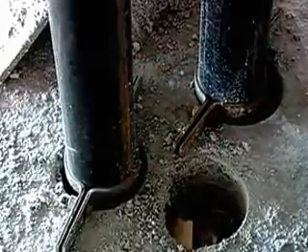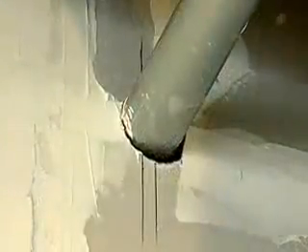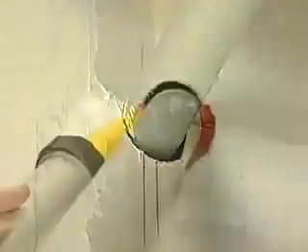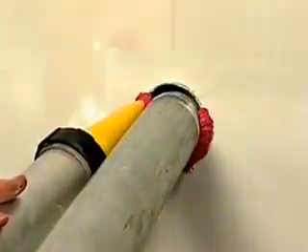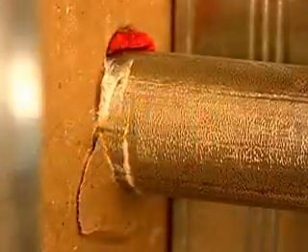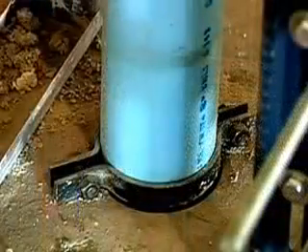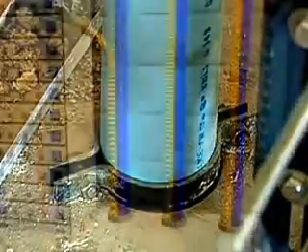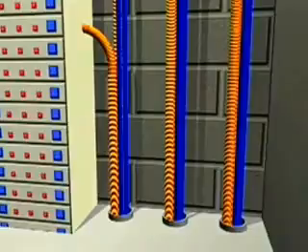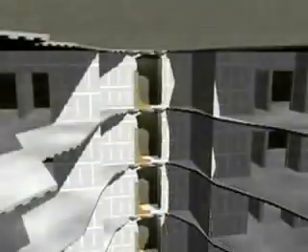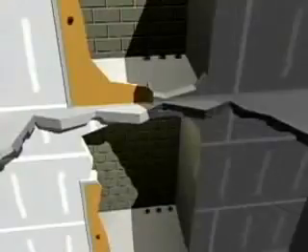Non-combustible penetrations like steel pipe and conduit are difficult enough themselves to deal with, but can usually be handled simply with Firestop sealant. Conversely, combustible penetrations present a much greater problem. Utility closets illustrate the point well because, in effect, what we are doing is stacking these compartments and adding openings in each floor, creating a chimney.